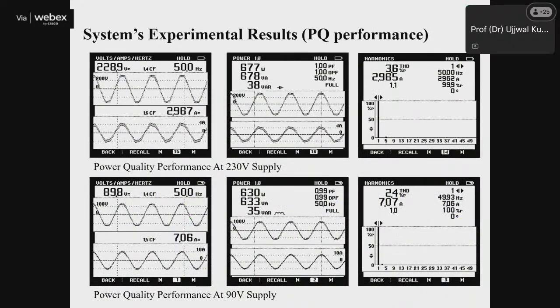And these are the power quality performances. This is valid here because we are presenting the results for the grid connected system also. You can see here the power factor is unity, and THD is 3.6%, which is less than 5%, meeting the IEEE 519 standards of power quality. And the THD at 230 volt supply and THD at 90 volt supply: in both cases, at very high voltage and at very low voltage, THD is 3.6% and 2.4% respectively, both less than 5%. So in the whole range of operation of the speed control of the motor, the system has very high power quality and less than 5% THD in the source current.